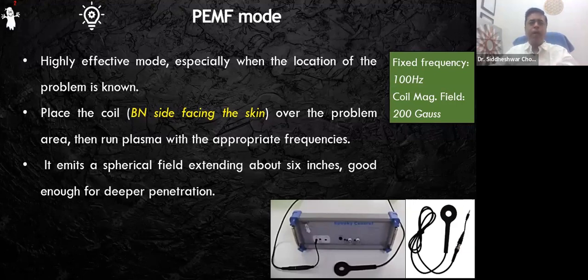In this case, again, the PEMF offers you a 100 Hz signal, and the magnetic field of the coil is 200 Gauss. It was way lesser when you use it normally with the Generator X or XM generator. But as I said, the Spooky Central is the amplifier unit, so you have a lot more power here, which is clearly evident from the magnetic field value of the PEMF coil. That is 200 Gauss. So where is the PEMF coil port? It is the first port from the left hand side on the front panel of the center unit.